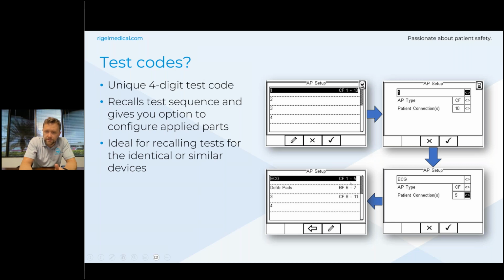Within some standards globally, they will have different leakage limits. So CF is a higher classification of applied part, and therefore the limits are much lower than what would be for BF. Now, in NFPA 99 in the biomed world for the US, that's not as relevant, and the AP Setup can be just tested for 10 applied parts. They're all grouped together. You're doing the sum of all the patient leakages, so it's not as relevant. But for anyone that's using IEC 60601 or 62353, that's where test codes can really be beneficial to the organization.